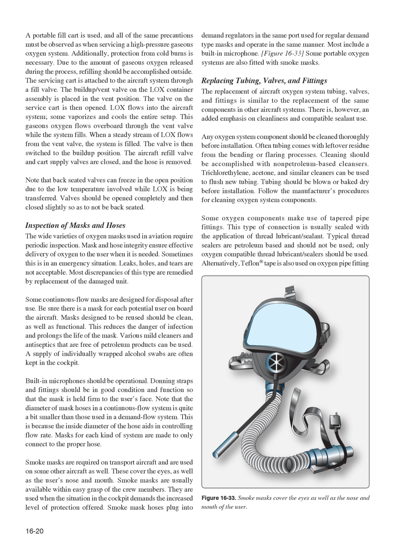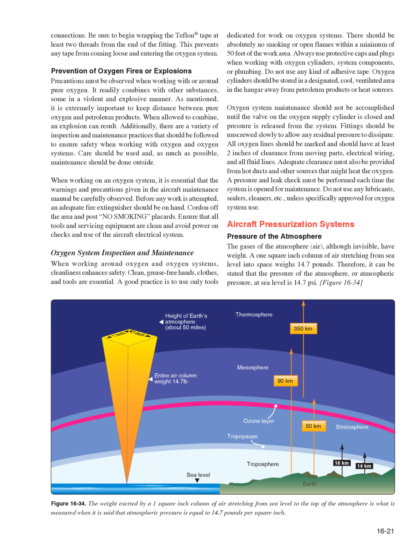Follow the manufacturer's procedures for cleaning oxygen system components. Some oxygen components make use of tapered pipe fittings. This type of connection is usually sealed with the application of thread lubricant/sealant. Typical thread sealers are petroleum-based and should not be used. Only oxygen-compatible thread lubricant/sealers should be used. Alternatively, Teflon tape is also used on oxygen pipe fitting connections. Be sure to begin wrapping the Teflon tape at least two threads from the end of the fitting. This prevents any tape from coming loose and entering the oxygen system.